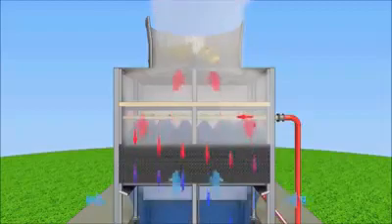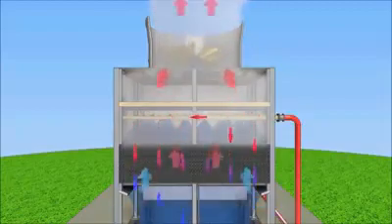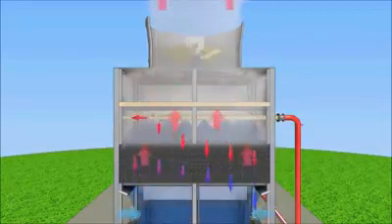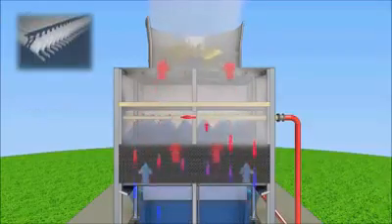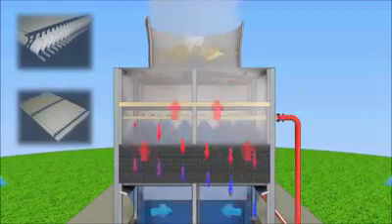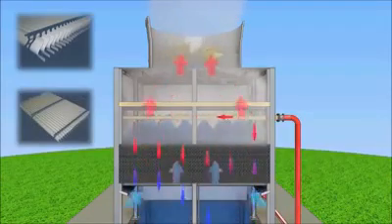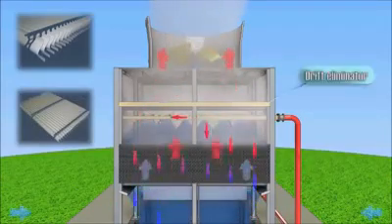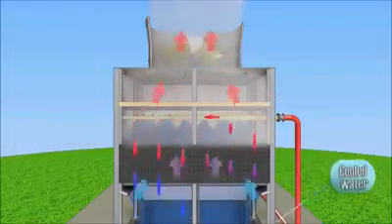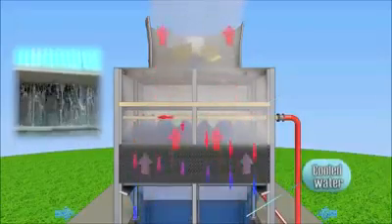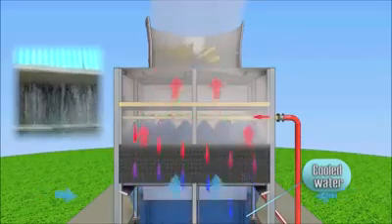Operating a cooling tower emits air saturated with water vapor and containing water droplets with a size of 100-500 micron. To prevent entrainment of water droplets, a drift eliminator is installed above the water distribution system. Cooling water moves down and flows into a catchment tank, and then is supplied by the pump to the technology.